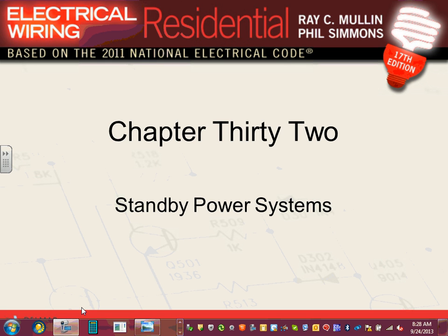Okay. So if you go to the standby power systems, the code book has three systems that you're going to need some type of generator for. One is called the emergency system, the other one is the legally required standby system, and the third one is the optional standby system. All these require generators.